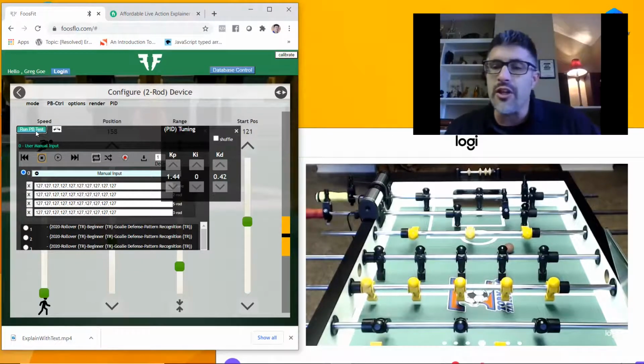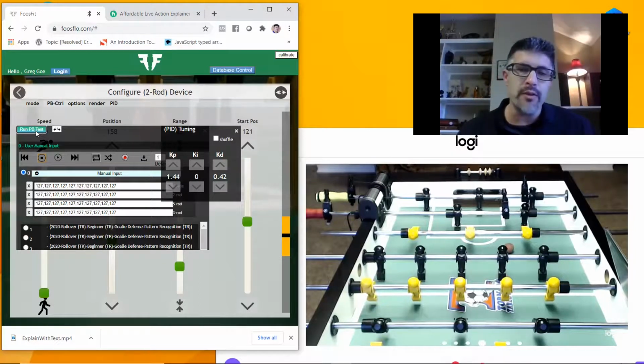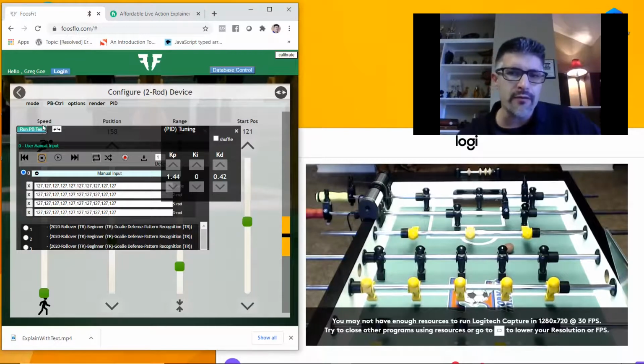Now the PID generally doesn't get off hardly ever, and you won't really have to set it much. It has nothing to do with the calibration per se. If you've been running your playback for a while and your PID settings are spot on with your test, but you notice they're off a little bit, you may still have to run the calibration test—because that's a different issue.